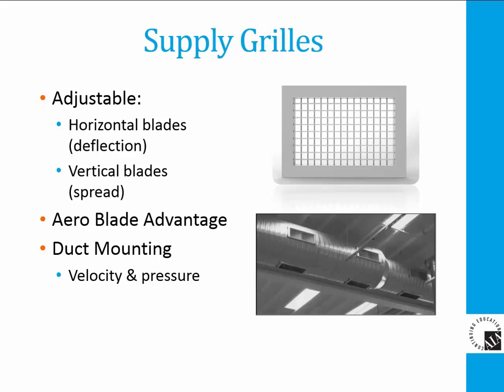Supply grills can be mounted at many locations on the walls including near the ceiling where surface effect assists longer throws and less drop, above the occupied zone where no ceiling surface is reachable, and commonly with modern design directly mounted to the supply air duct. Horizontal blades can assist in limiting drop by deflecting the air jet upward. Vertical blades can be used to control the throw distance by spreading the air horizontally to change the air pattern from directional to radial.